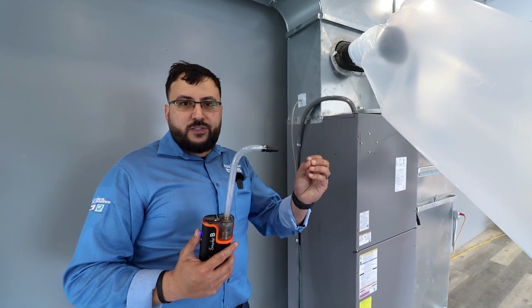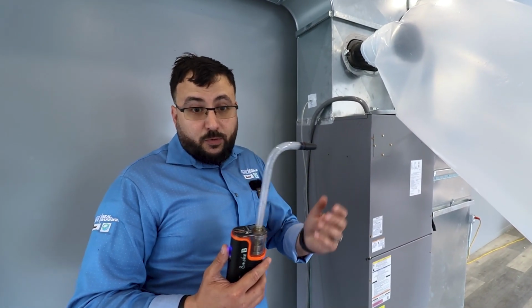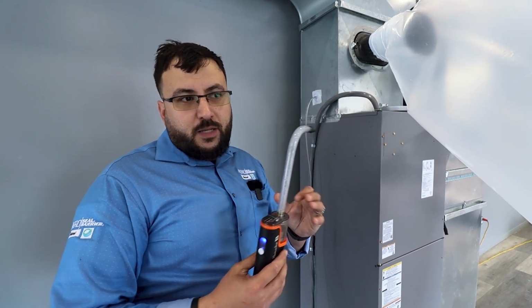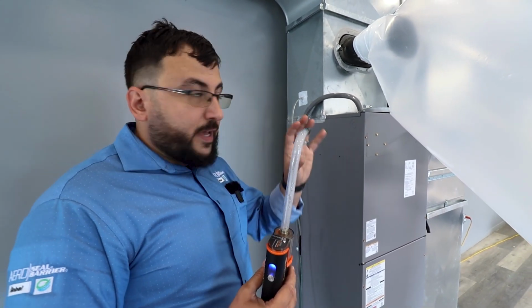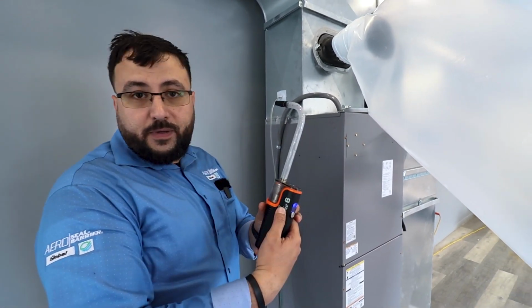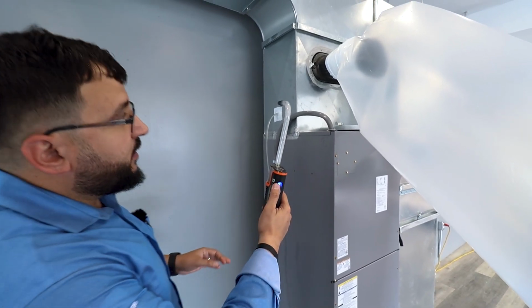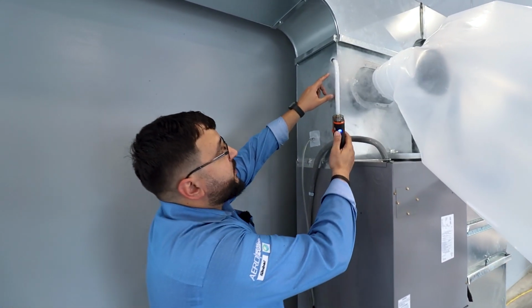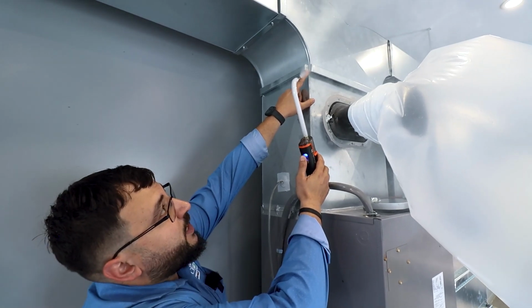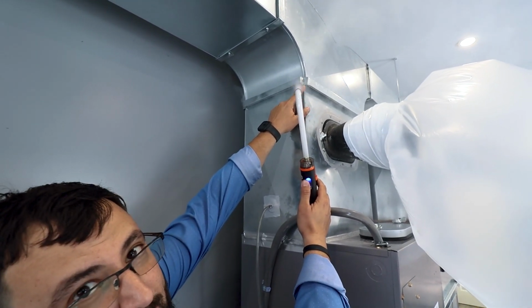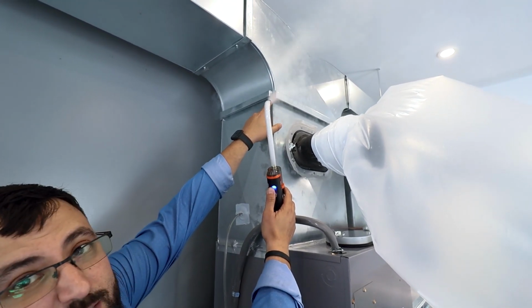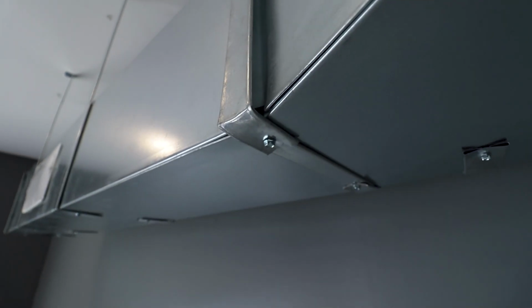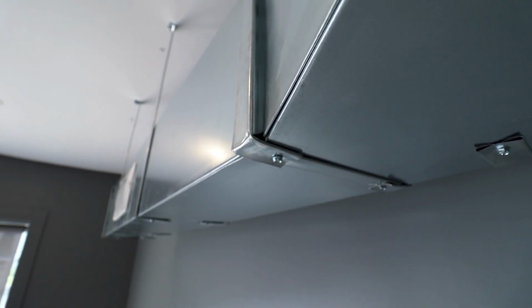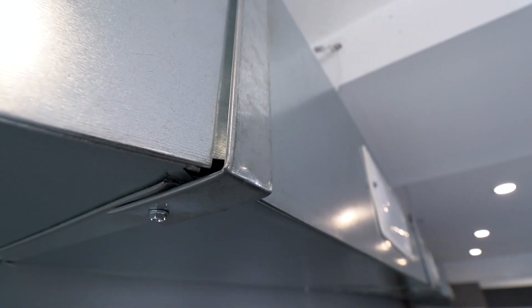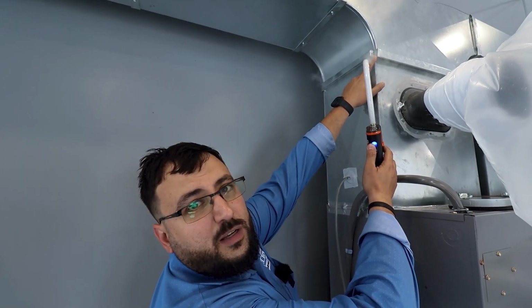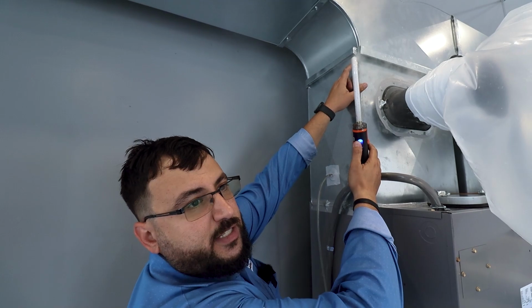To visualize air leakage, because air is invisible, we have a fog machine, and sometimes to test and visualize where the leaks are, we'll put in a bit of smoke. So in this area, as we can see, you see how air is being pushed out. This is what we call a mechanical joint, and there's no seal. Unfortunately, one of the issues most systems have is that every time the ducts are assembled, not every corner or junction is actually sealed.